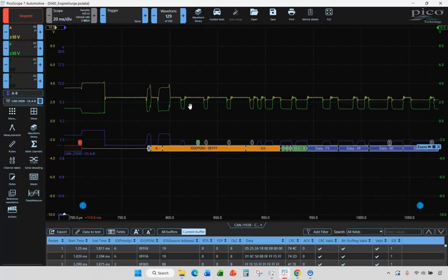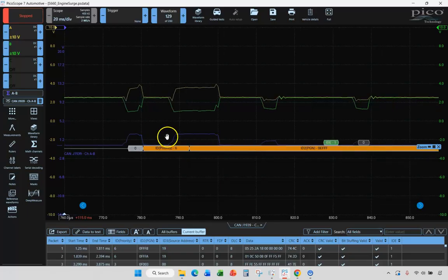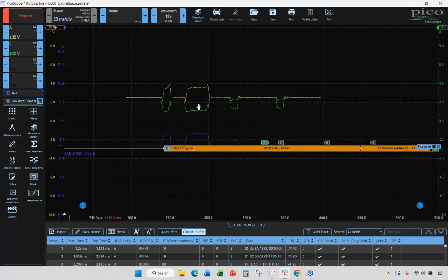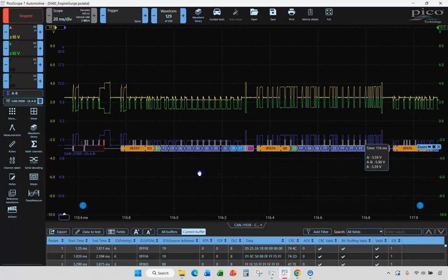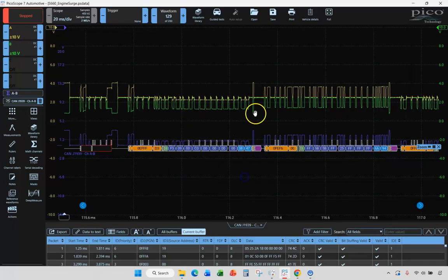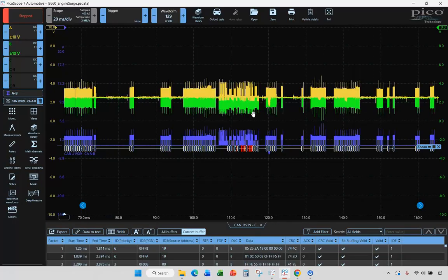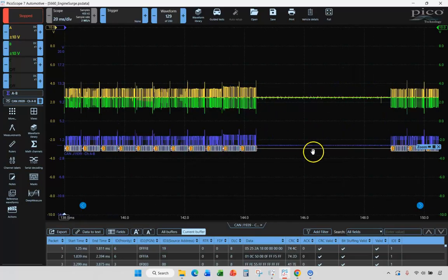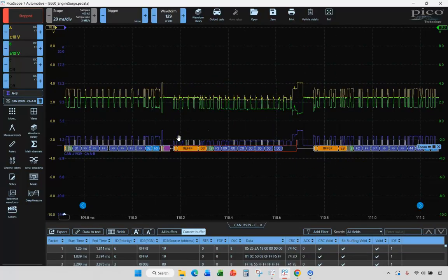Maybe one thing to point out here, if we're looking at the scope data, we can see arbitration at work. We had our priority, we had some other device, and then at some point some other controller lost arbitration, and so we're able to then continue communicating D3. Some controllers may be able to acknowledge this at times, and you can see by the acknowledge bit, everybody apparently thought this was okay. It's whenever this device starts stepping on other messages that we end up with a problem.